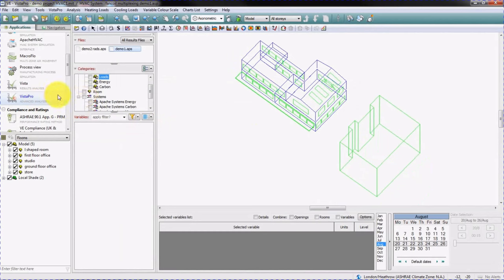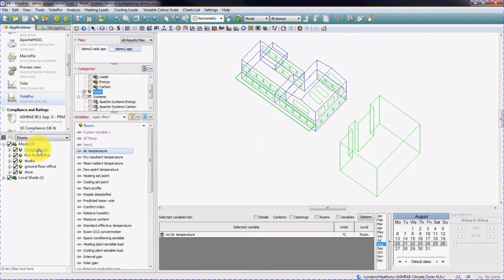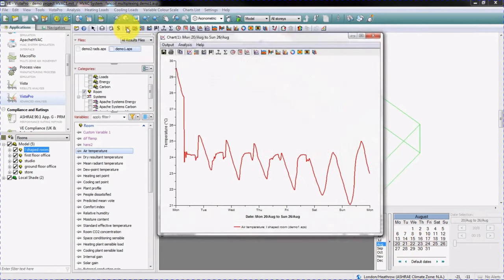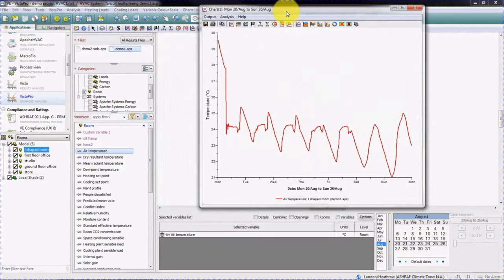Let's look at room temperature in the L-shaped room. We'll select room results, select the L-shaped room, select air temperature, and look at the results for a week in August. Let's create a graph. You can see the temperature in the room is being controlled to the set point from Monday to Friday during operating hours.